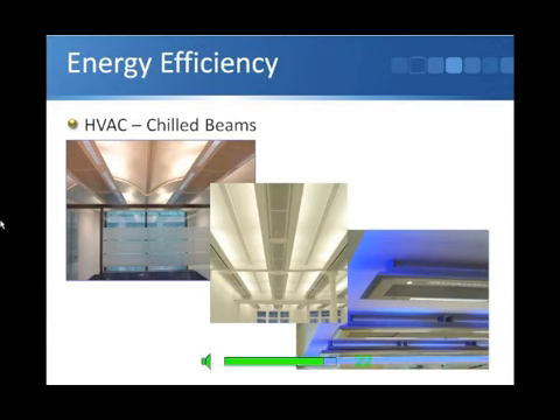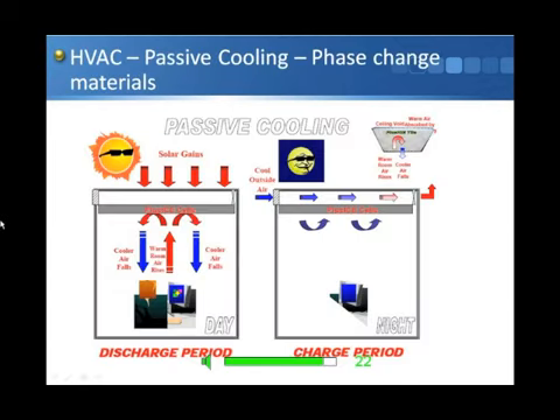We have active chilled beams and passive chilled beams. Speaking of passive, of course, that brings me on to the whole idea of, if you like, surrogate thermal mass through the use of phase change material. And this is material which, in this diagram, I've indicated as plus ice cells, and these are containers which contain a material which is solid within the plastic container, but it changes into a liquid as it absorbs heat at a constant temperature. It's obviously a latent heat because it's changing from solid to liquid, and as it does that, it provides a cooling effect to the room.